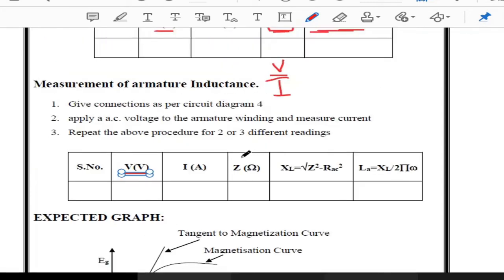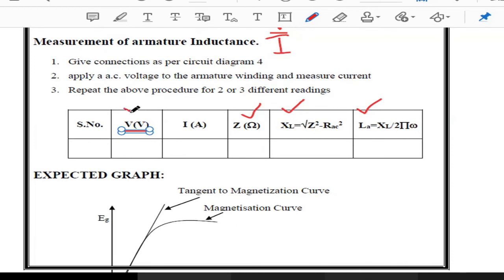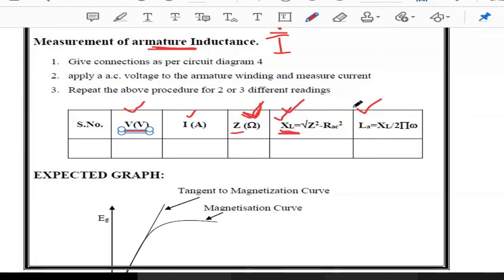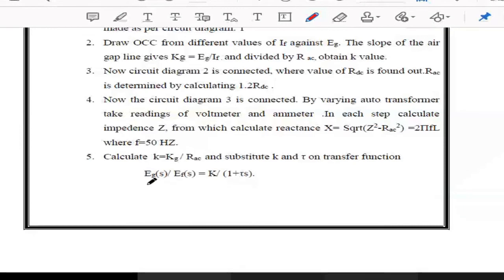We also need to calculate impedance, inductive reactance, and inductance. Values for voltage and current for measuring armature inductance will be provided. After finding impedance Z, the inductive reactance is calculated as: XL = √(Z² − R²). Then the inductance is found as: L = XL / (2πf). All these quantities — resistance, reactance, and inductance — are needed to determine the transfer function of the DC generator.